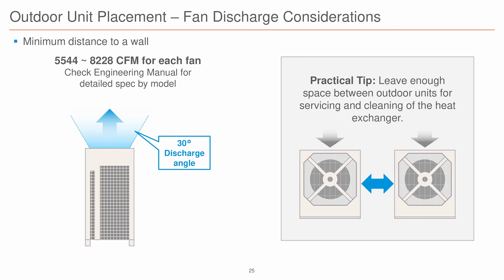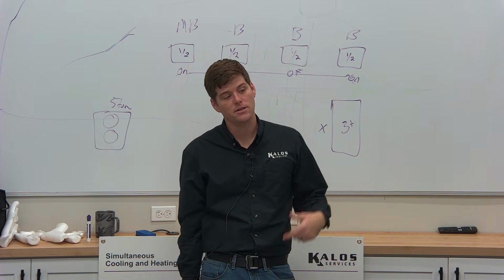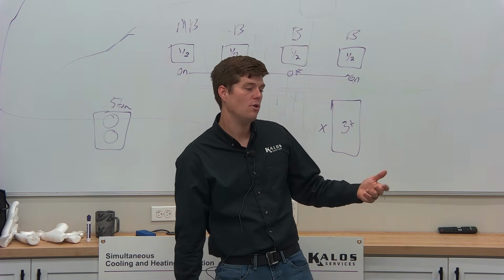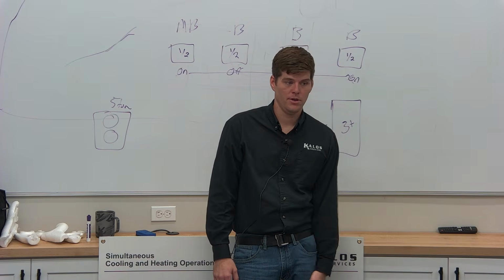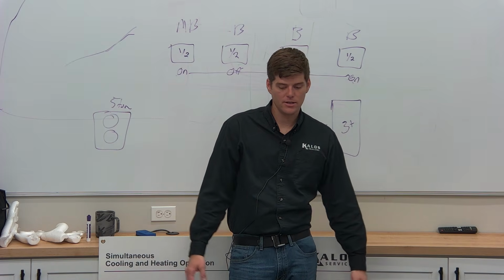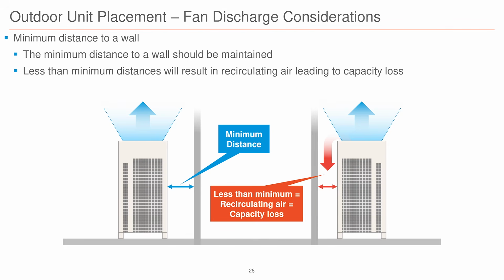It causes more issues. Outdoor unit airflow, discharge, stuff you probably don't even need to know. Discharge at a 30-degree angle. Why is that important? You don't want to put a unit right up against a wall with an overhang. You're going to find that the hot air that gets discharged out gets recirculated back around, reduces capacity, causes service issues. It's that one call that you always get a high-pressure trip on in the middle of summer, right? It's just not a good idea. Use your brain. Outdoor unit placement, that we talked about before, right? Just be mindful of that 30-degree discharge.